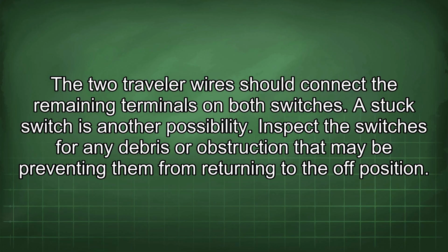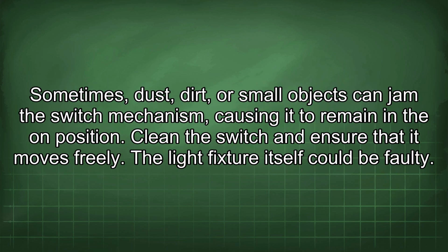A stuck switch is another possibility. Inspect the switches for any debris or obstruction that may be preventing them from returning to the off position. Sometimes, dust, dirt, or small objects can jam the switch mechanism, causing it to remain in the on position. Clean the switch and ensure that it moves freely.